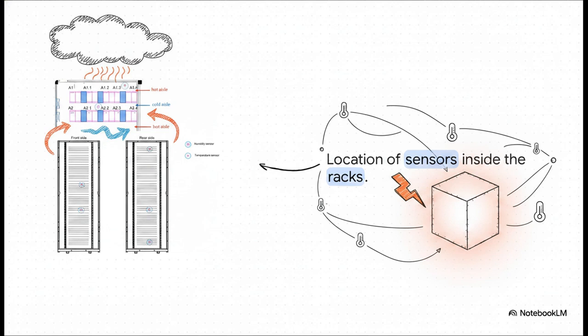Just take a look at this digital map of 18 active server racks. This brilliantly illustrates the careful placement of 54 temperature and 5 humidity sensors. They're specifically set up in the cold aisles where the air comes in and the hot aisles where the exhaust blows out. Because everything is directly integrated, if a sensor catches a temperature spike, the operator doesn't just see a warning line on a spreadsheet, they see the exact 3D spatial location of the problem area.